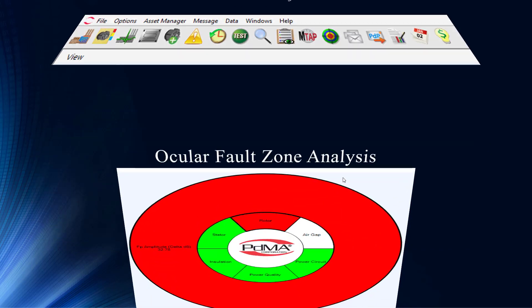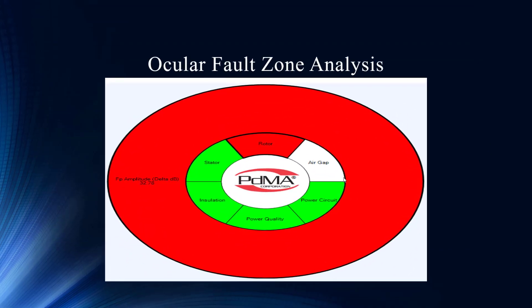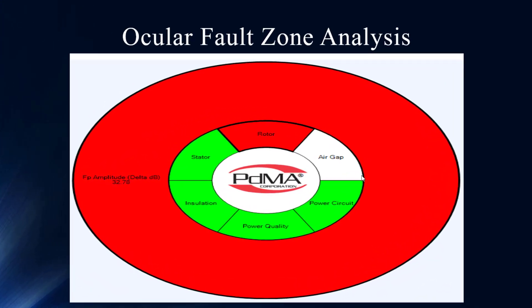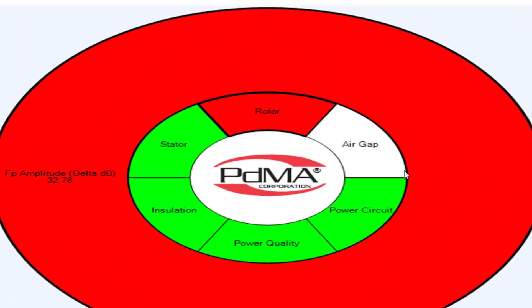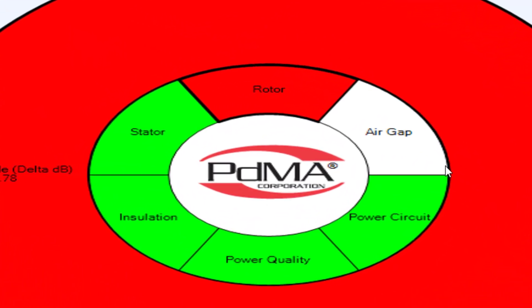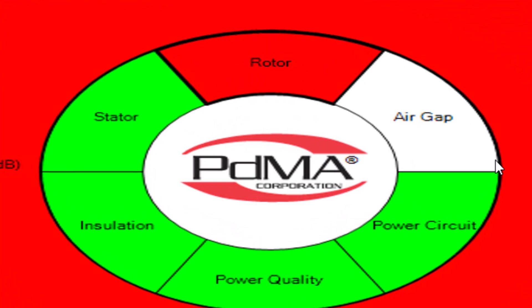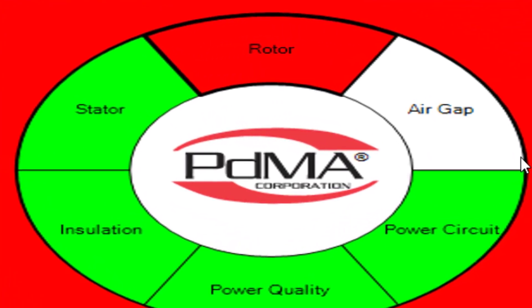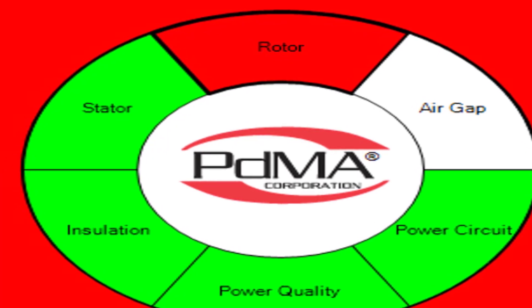When we click that, it's going to send us directly to this screen here — it's called our ocular fault zone. If you see anything, we usually say red is bad, and there's a lot of red on this fault zone. You can see we've split this up into our six fault zones, so we have all six covered here. I see 32.78 pole pass sideband amplitude — what determines that number, what puts that in red?